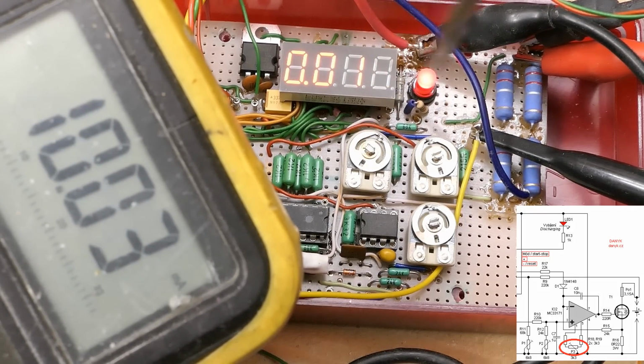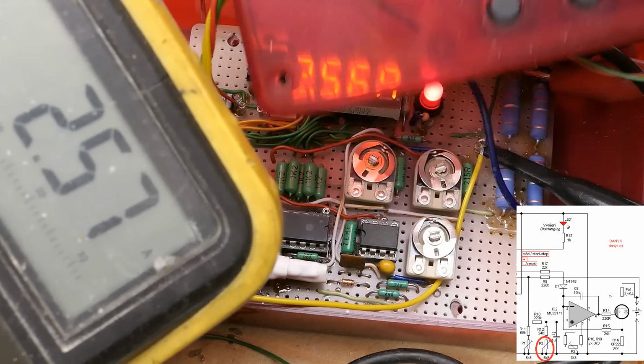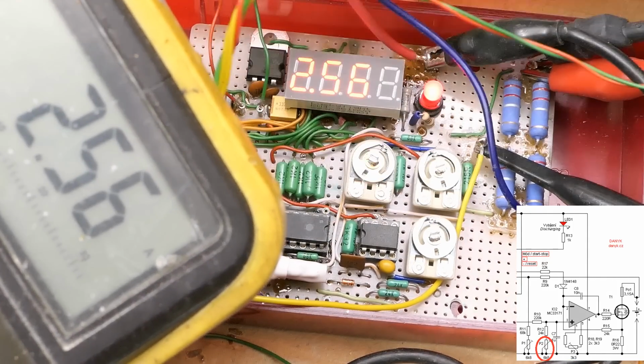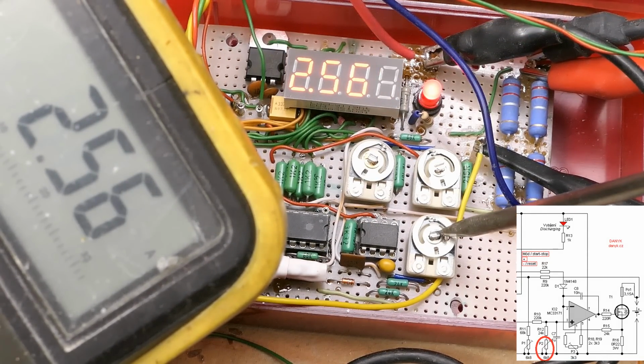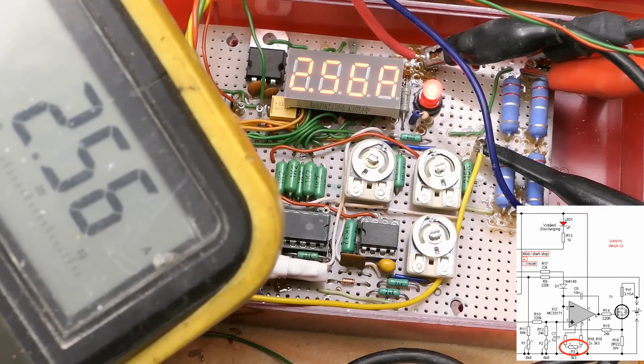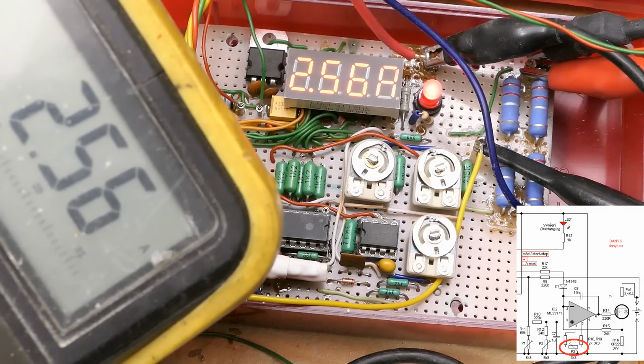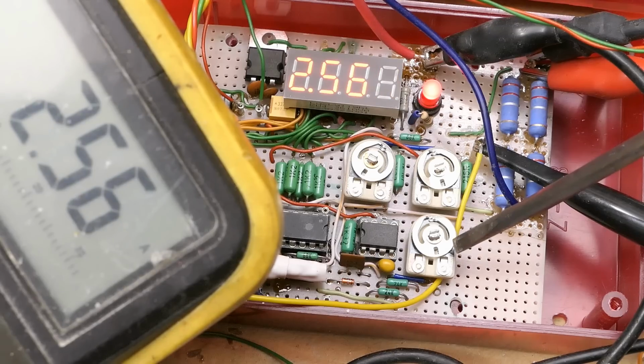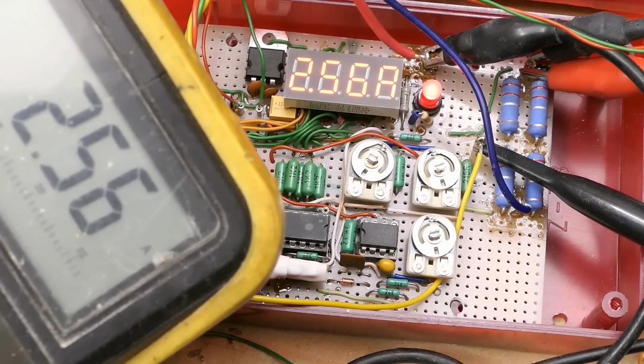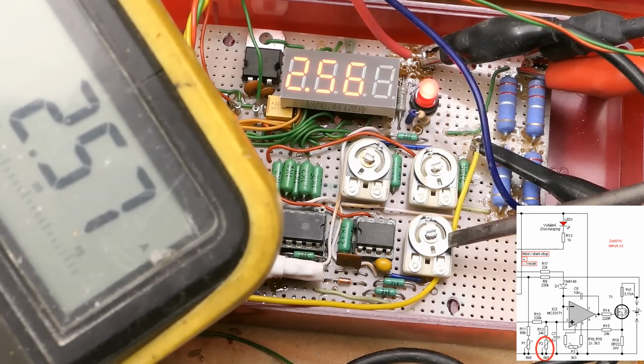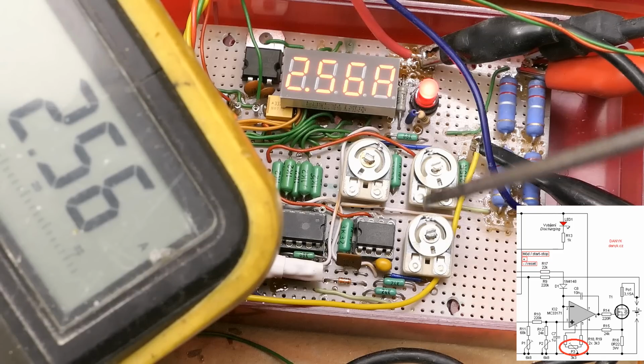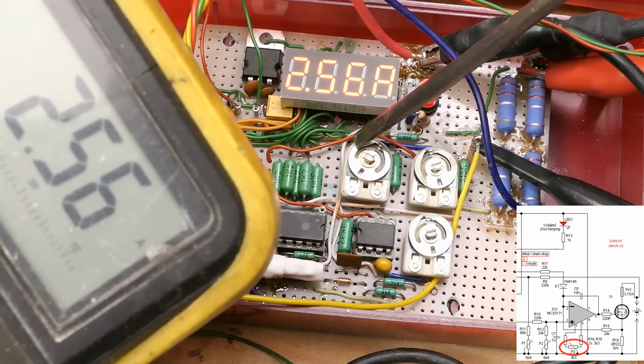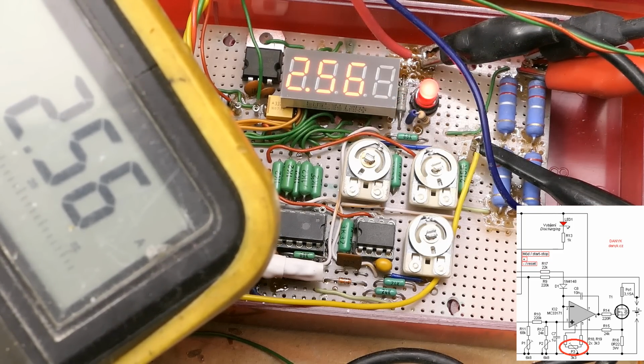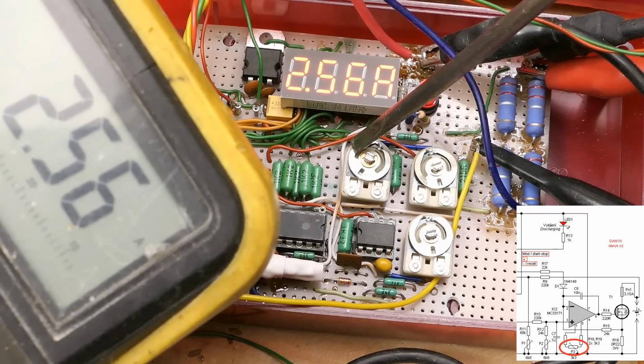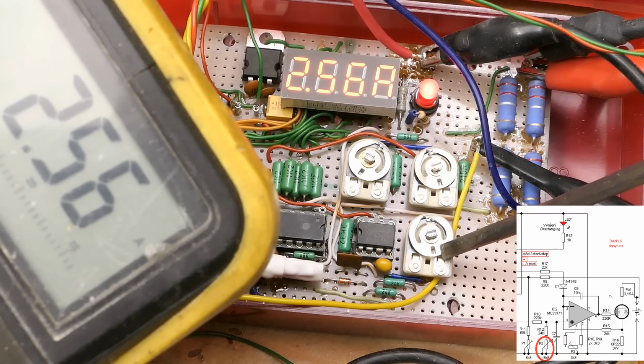And that's about it. And you might have to reiterate a couple times. You set it back to the maximum current and adjust the current potentiometer. And then you go back to the minimum current and adjust the offset potentiometer. And that's because both potentiometers actually influence both ends of the range. But the current potentiometer mostly influences it at the top of the range, and the offset potentiometer influences it mostly at the bottom of the range. That's why you're setting the offset at the minimum current, and the current potentiometer at the maximum current.